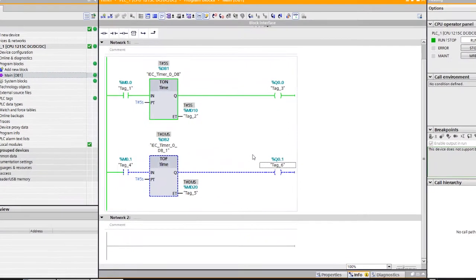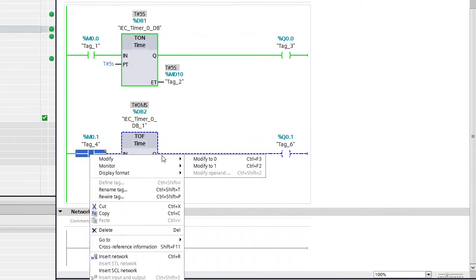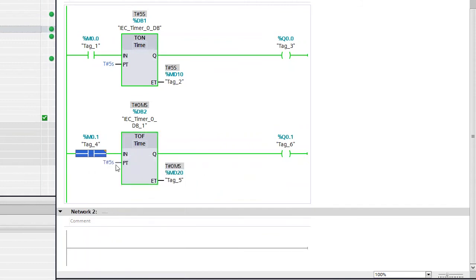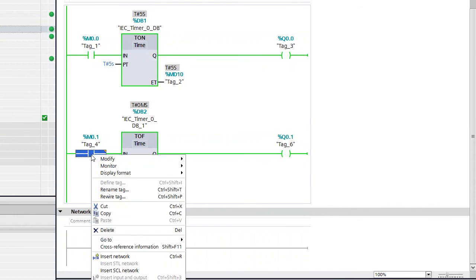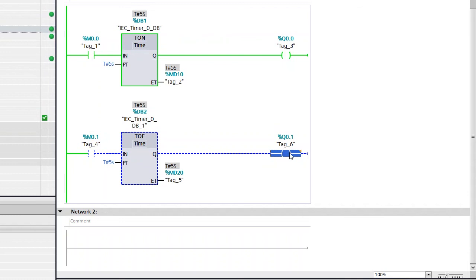Minimize and click Monitor. Now we can test the off-delay timer. The instruction starts in the open state — let's close the input first. The off-delay timer is activated when the input goes OFF. Right-click, Modify, set to 0. Now you can see the output is still high for five seconds until the preset time is done — then it goes OFF. This means off-delay: to go OFF, it takes the specified delay — the preset time.